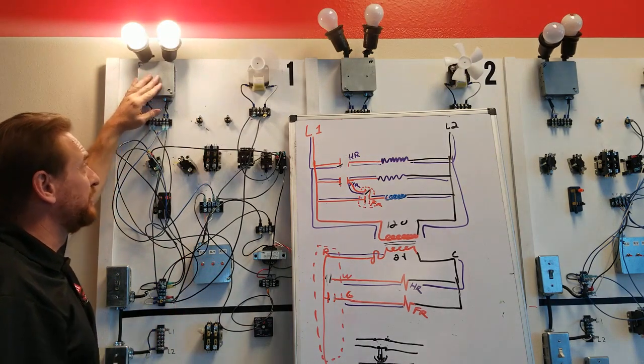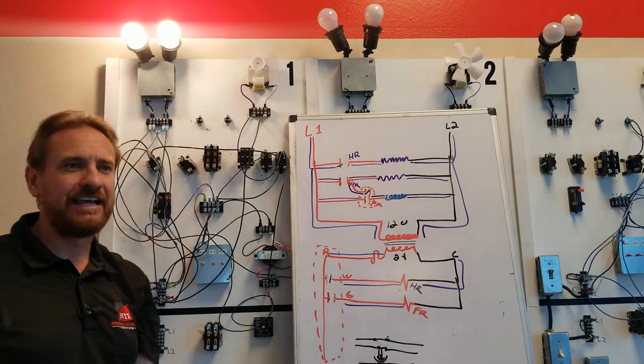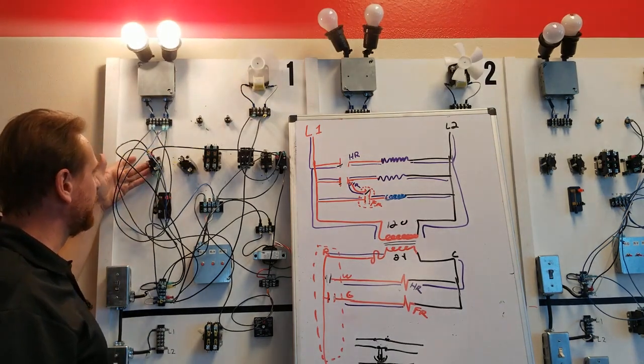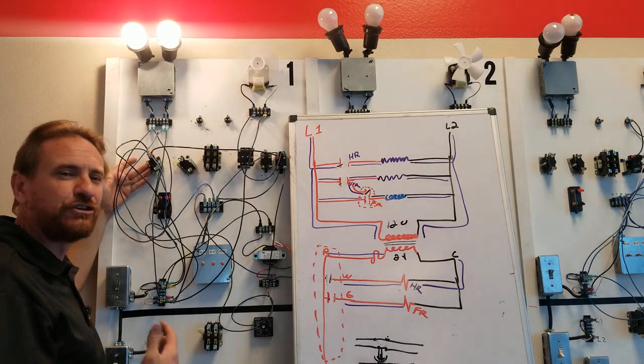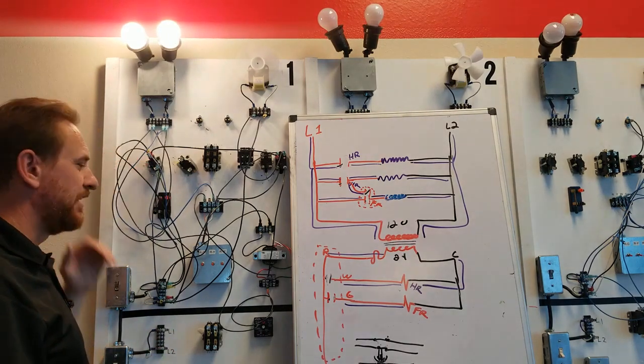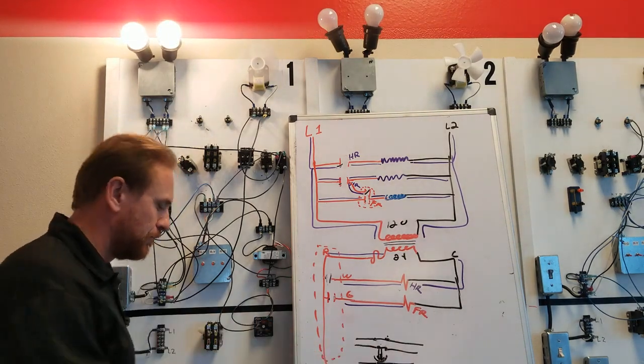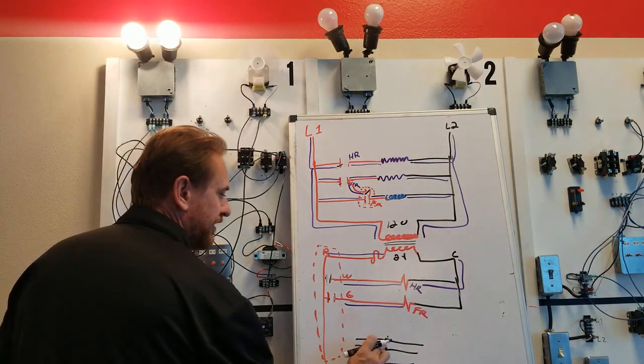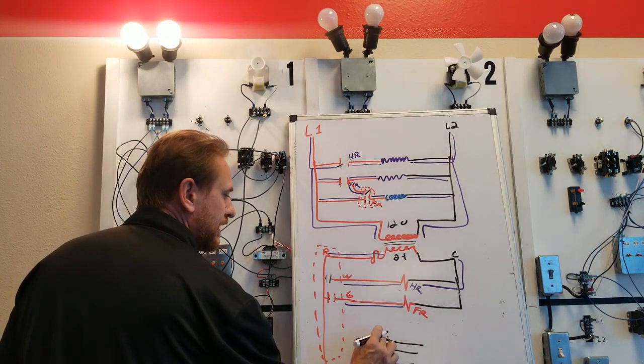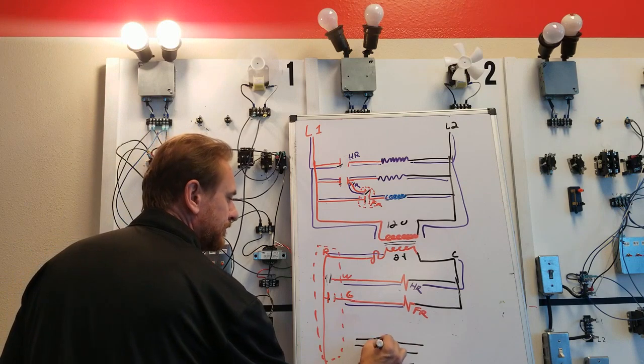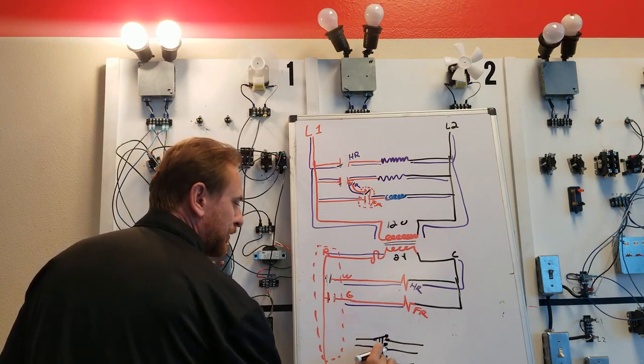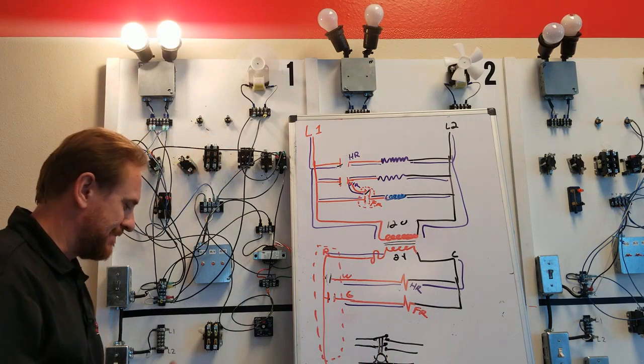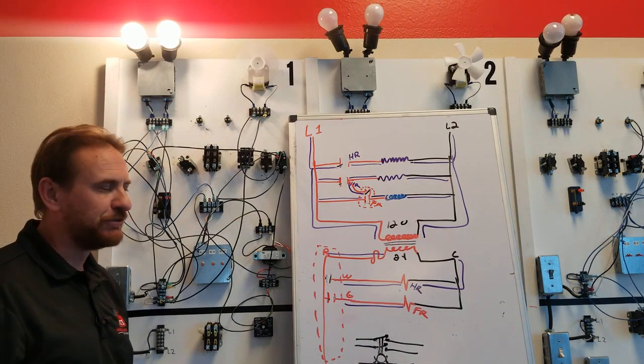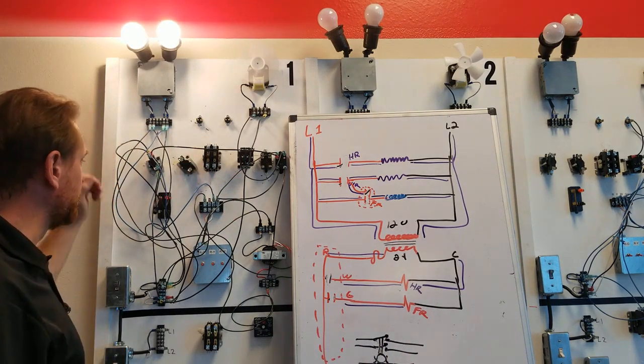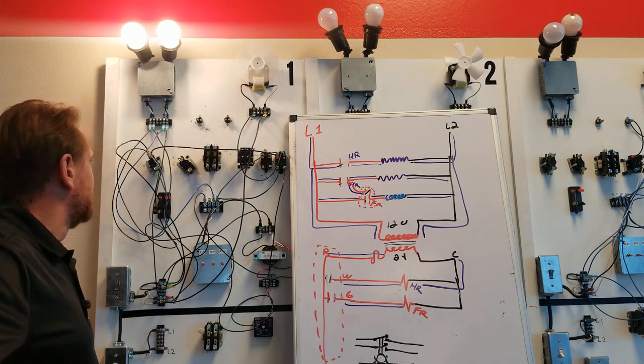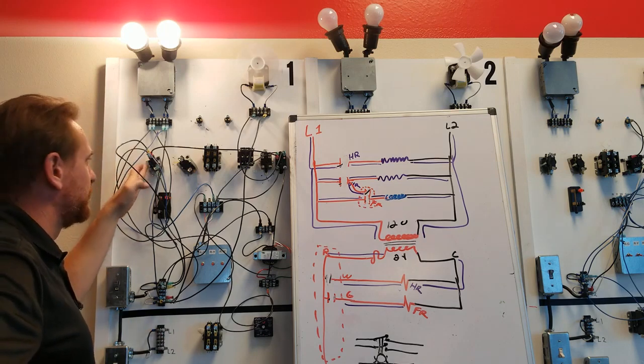In this case, even though my heat elements are still on, I'm still moving that air into the house. And it takes time, even though I've killed the 24 volts, it takes time for this to cool off. Once this cools off, that bimetal is going to pop up. When it does pop up, it's going to shove this switch open, and it's going to cause this switch to open, and this will be popped up in my horrible, horrible drawing. And that's the essence of how that sequencer is working. So we just give it a little bit of time. It'll cool off shortly, and then it will shut off.